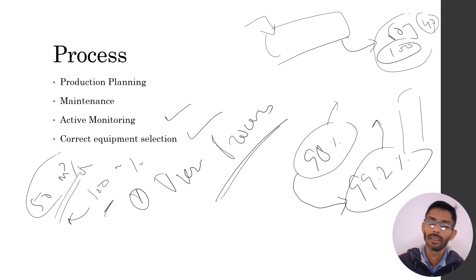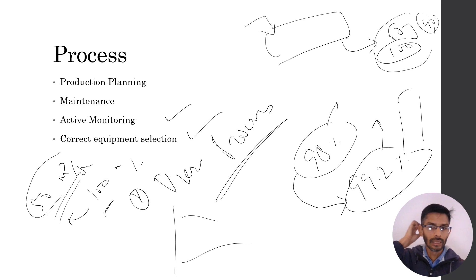Correct selection of equipment is also very important. A thorough study should be done before selecting equipment. Suppose you need a pump for 50 meter cube per hour, but without proper calculations you select a 100 meter cube per hour pump based on some assumptions. Then you will be running this pump at only 50 meter cube per hour, while its best efficiency point is at 100 meter cube per hour. If you deviate from the best efficiency point in pumps, it consumes a lot of energy. So all these things should be taken care of.